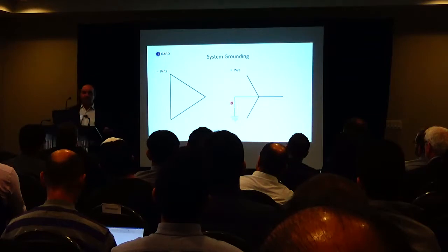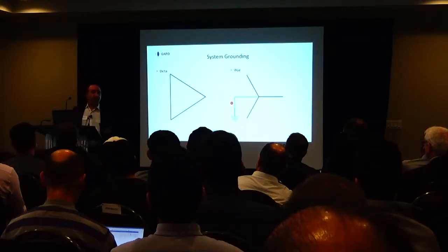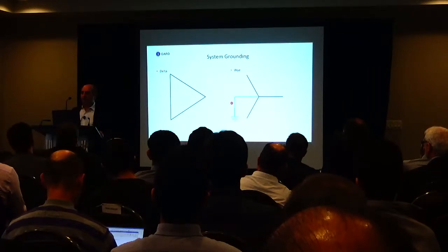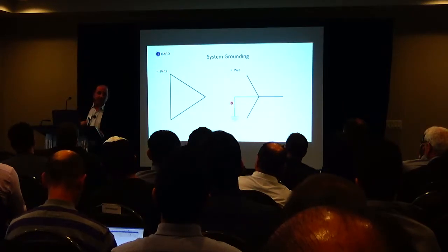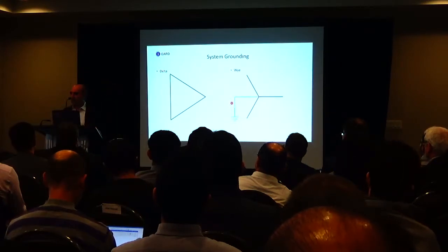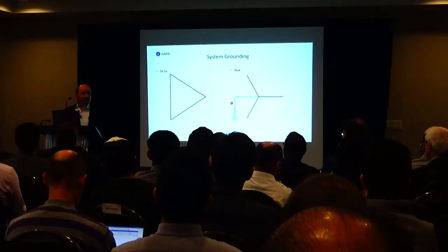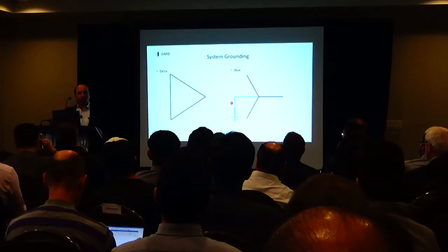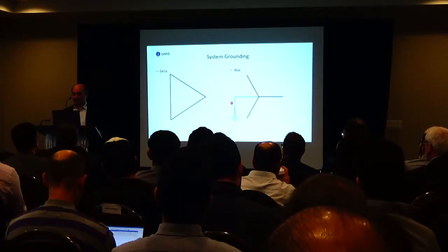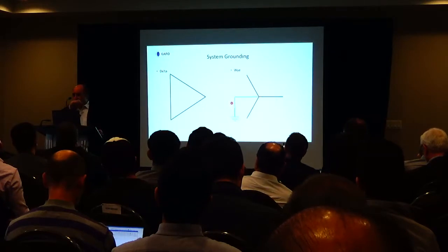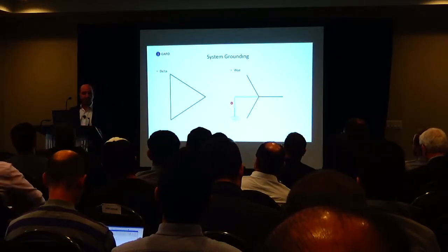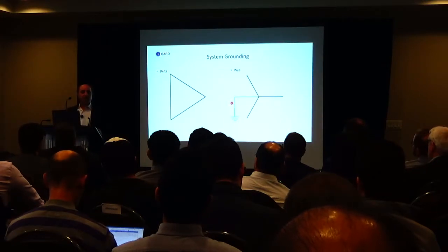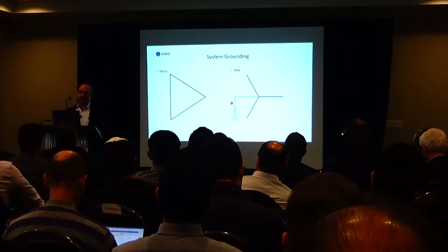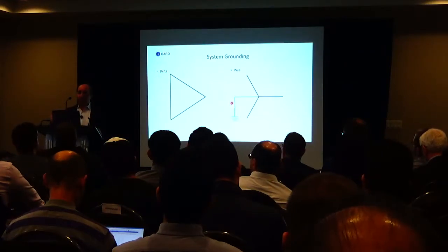Anyways, incident energy is directly proportional to time. A resistor is not going to lower incident energy. What it does do is it decreases the probability of a single phase to ground fault, which is the most typical fault that you can have in the industry, from propagating to a 3-phase fault, and hence lowering the probability of having an arc flash event. So that's why resistance grounded systems are arc flash mitigation techniques, because they lower the energy at the point of the fault such that you have no damage, very little damage, and you have an arc flash mitigation technique.